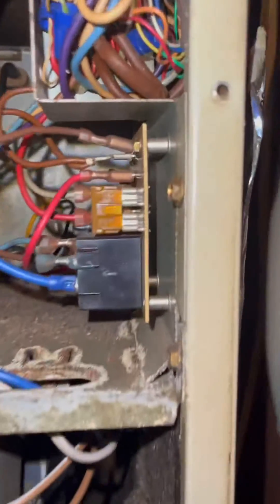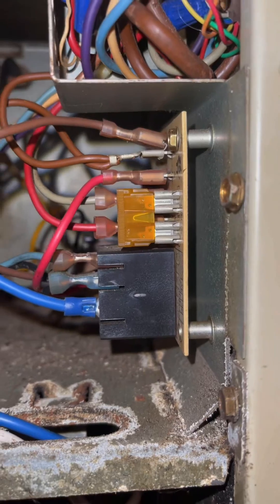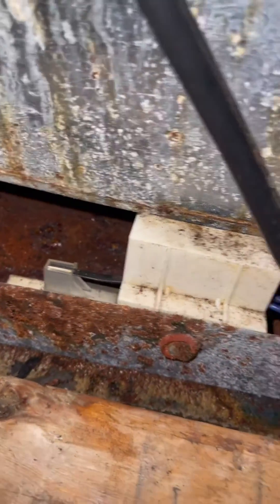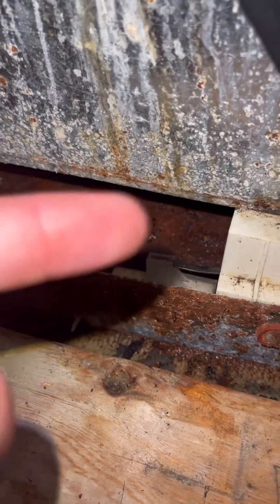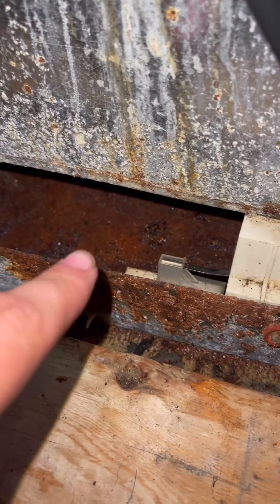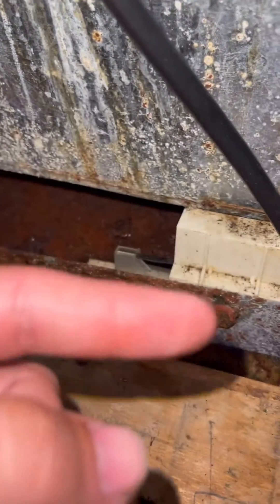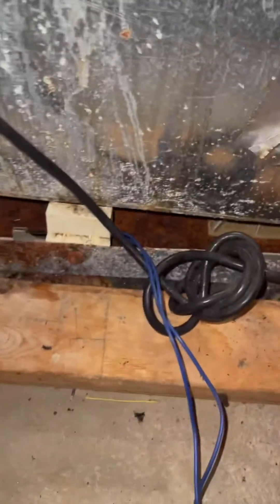The fuse you're going to want to look at is going to be here — make sure that it's good. As you can tell, it's running now. Here's your condensate pump and right here is the float switch. This little piece right here rises up as the water fills up in here. It's leaking. If it fills up, your little float will come up and it will trip this.